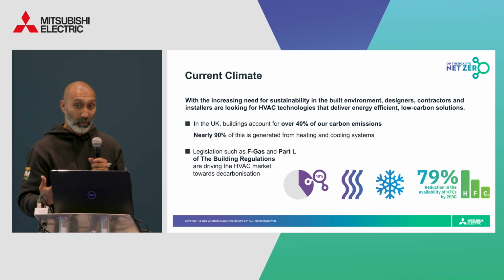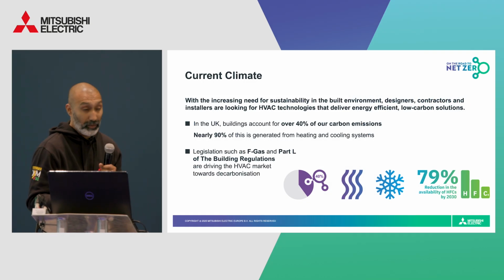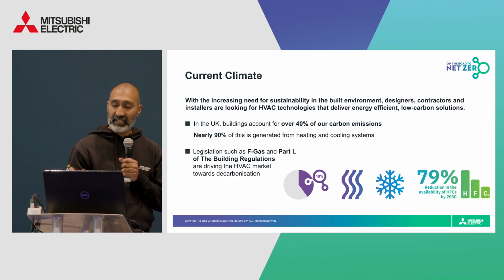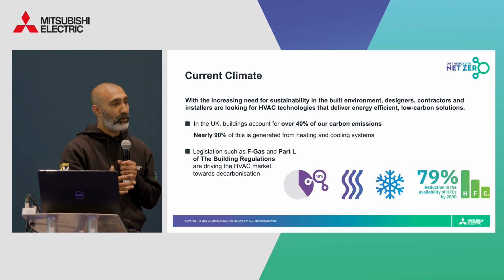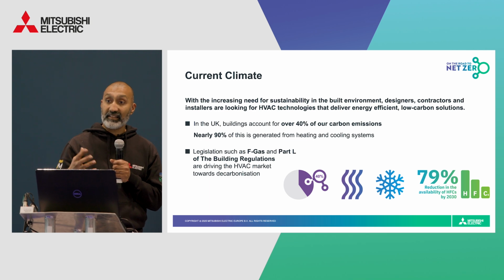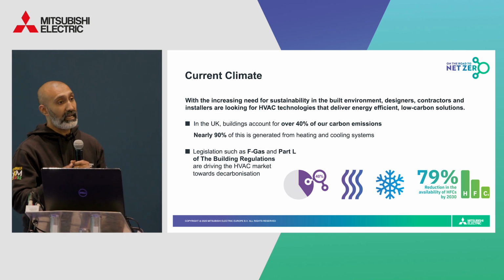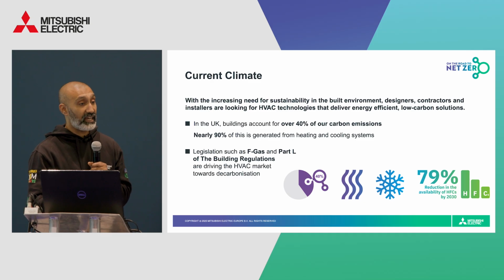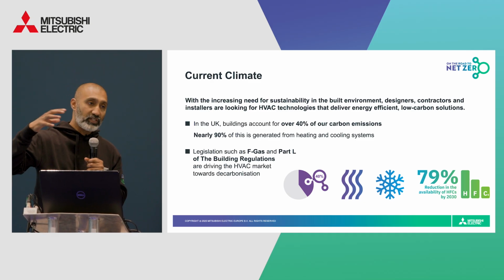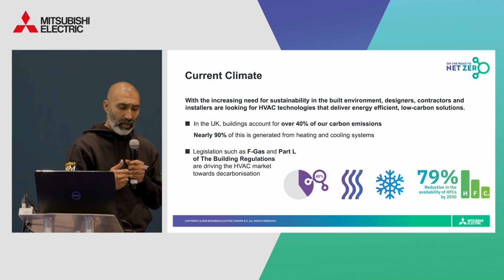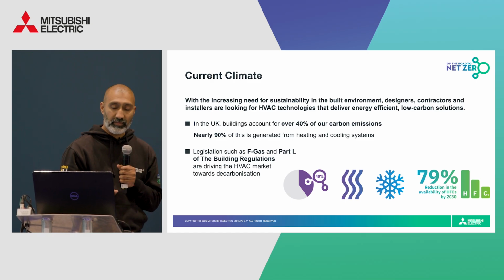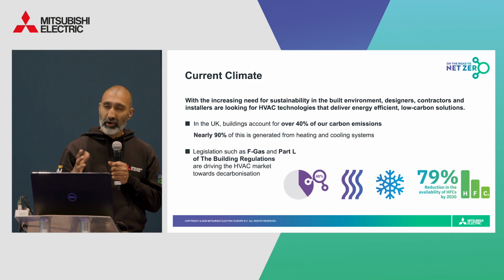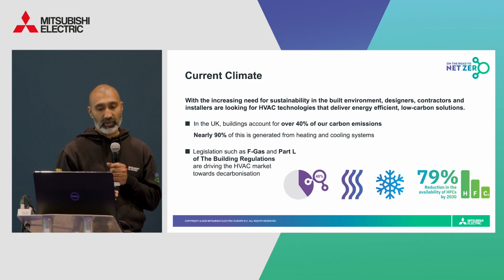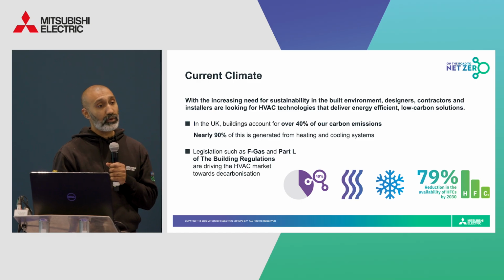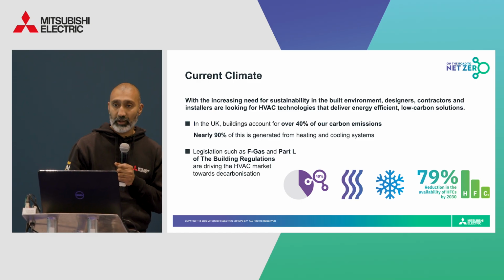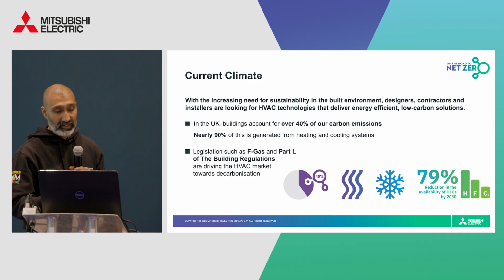Now, we know the world is getting warmer, and this is because of human activity, making immediate action essential. And here in the UK, Part L of the building regulations sets the standard for energy efficiency by promoting better insulation and efficient heating and cooling systems, all aiming to reduce operational carbon. Now, one significant contributor to carbon emissions is F-gas, which accounts for around 3% of the UK's total emissions. And these gases have a global warming potential thousands of times that of CO2 and can remain in the atmosphere for hundreds of years.